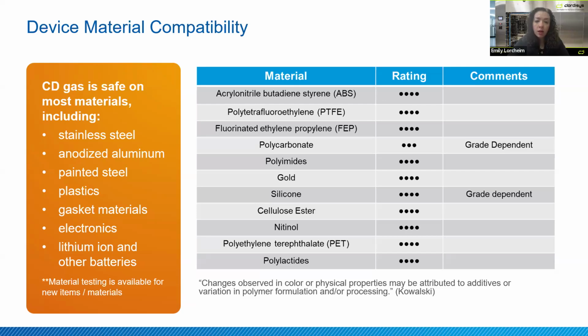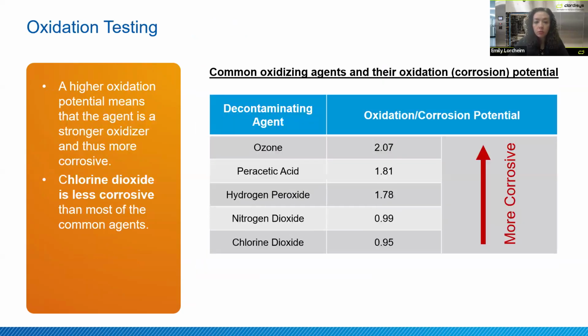Now, the big thing is that it is compatible with cellulose materials and electronics like embedded batteries. That's different than most other alternative sterilization modalities, and ethylene oxide isn't compatible with batteries. Like I mentioned, chlorine dioxide is an oxidizer. However, chlorine dioxide is the most gentle of those.